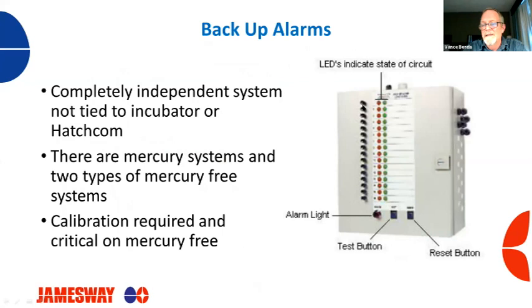It's an independent, separate system. Now, there are two systems out there, and the older system is a mercury type system, and it uses a three conductor wire between the control panel and the thermostat. And the mercury free system, we pull a five conductor from the control panel to the thermostat, but it uses the same control panel. So if you're running a mercury system, everybody knows mercury is going away sometime in the near future. So we may have to convert your mercury system over to a mercury free system, which is going to require that we pull that old three wire out and pull five conductor in and change your thermostat boxes.